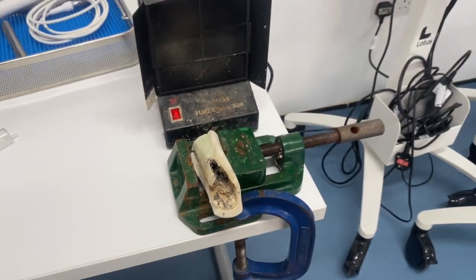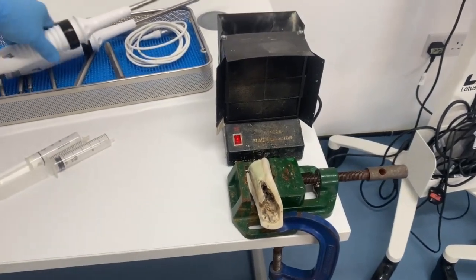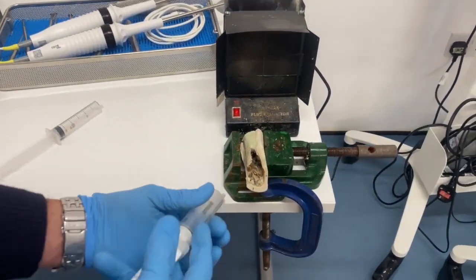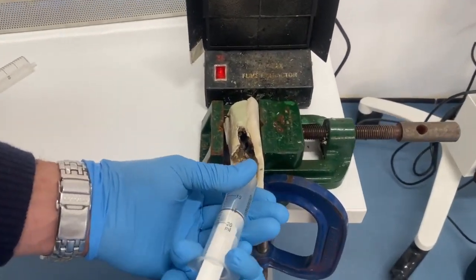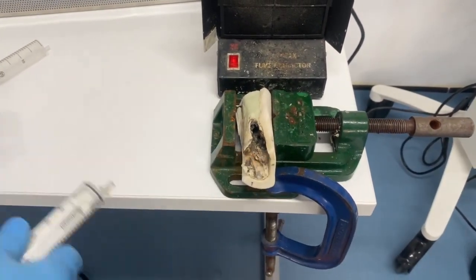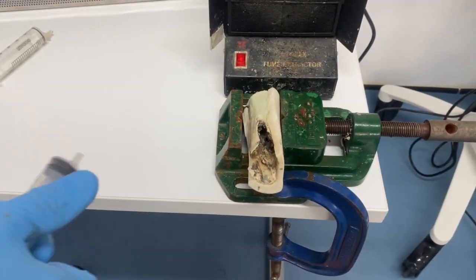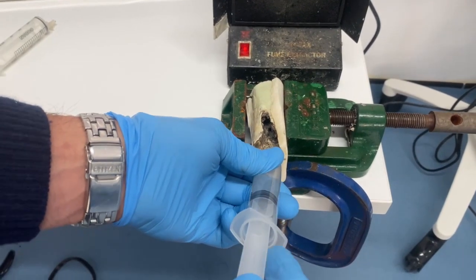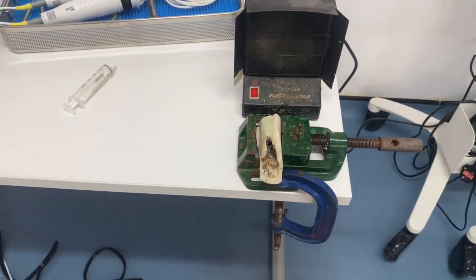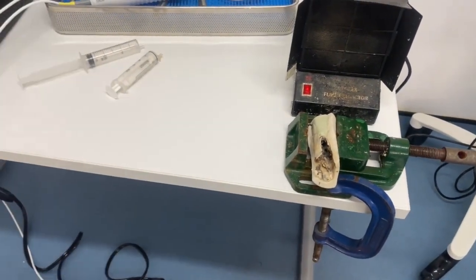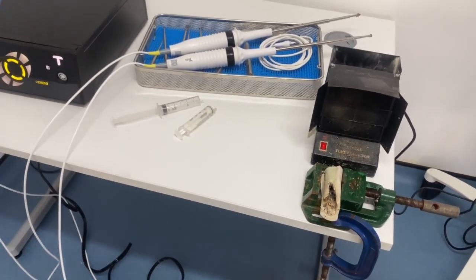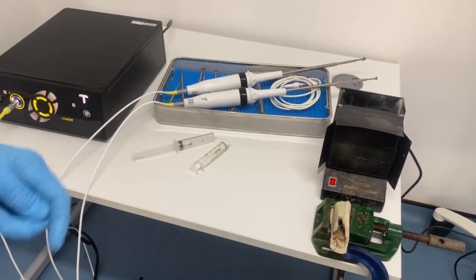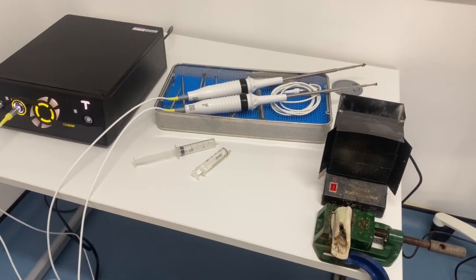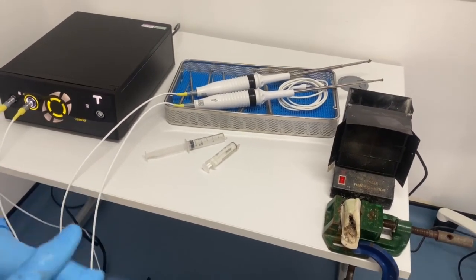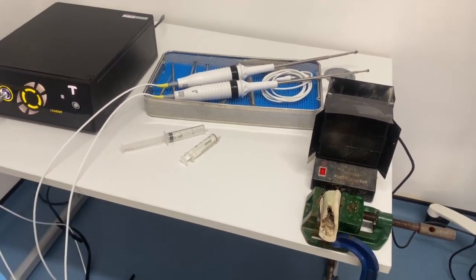And as with the piercer, use the syringe full of saline after each set of 3 scoops, and you pull all of that saline out again so that it's dry. You don't want saline left in there because the ultrasound can actually boil that saline, and that might do some thermal damage. It's all very easily put in and removed with the suction lavage system.